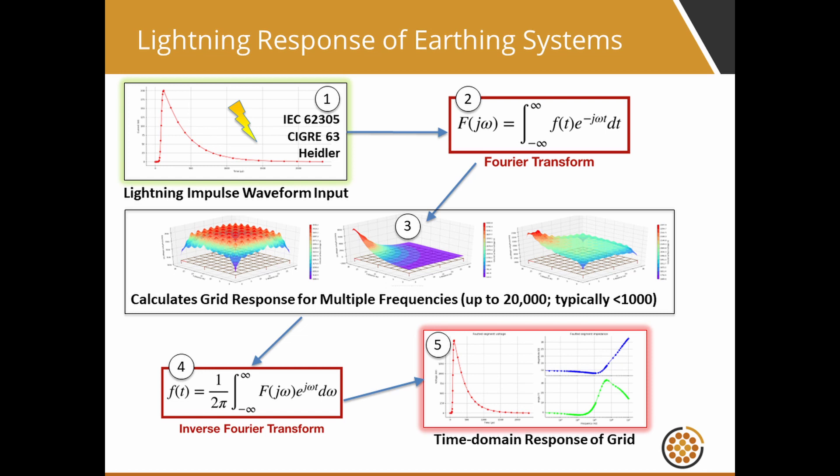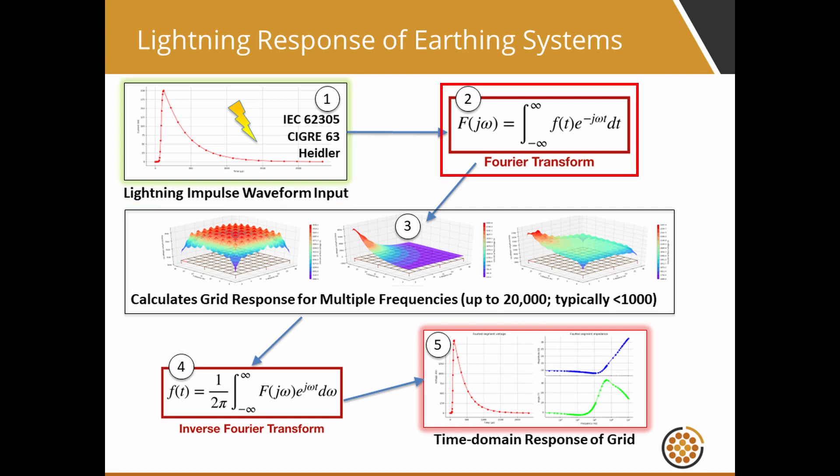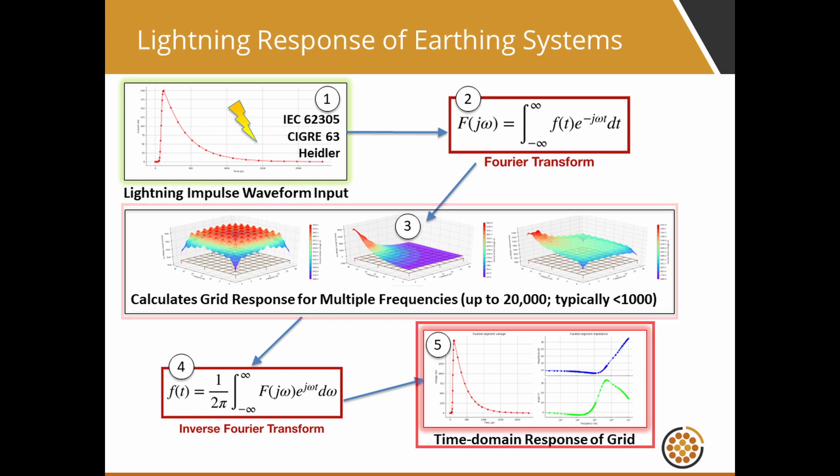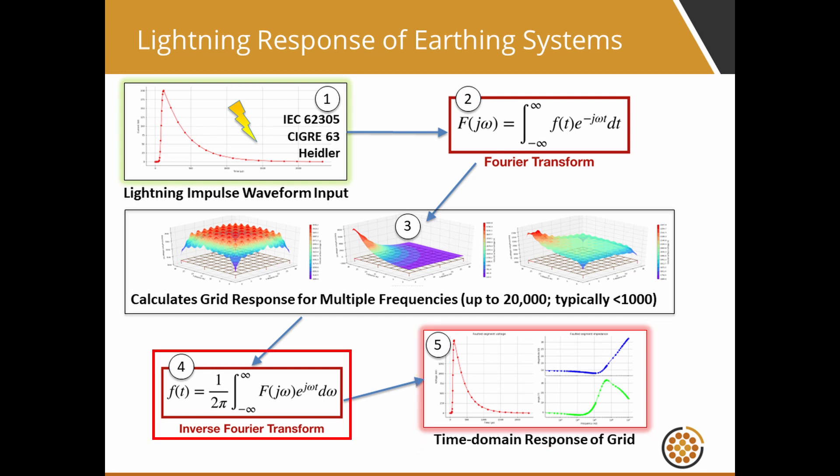Safe grid earthing software can perform calculations in the time domain such as for lightning currents by considering that a transient waveform is composed of many different frequency components and uses forward Fourier transforms to decompose the waveform. The response of the earthing system to the individual frequencies of the lightning current is then calculated in the frequency domain. The resulting time domain response of the earthing system is obtained by applying the inverse Fourier transform to all of these responses.